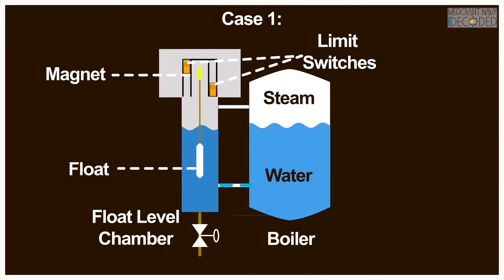Now let us see the animation of the low water level float and try to understand its functioning through three important cases. In case 1, you can see the float level chamber associated with the boiler. The white colored part is the steam part and the blue colored part is the water part. The float inside is attached to a magnet, and this magnet is inside the switch unit, which has limit switches fitted along with it.